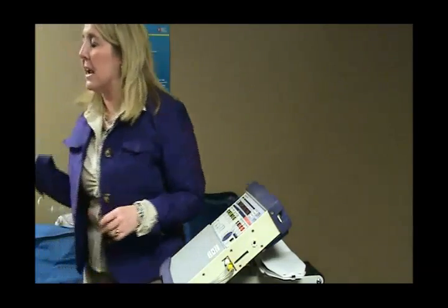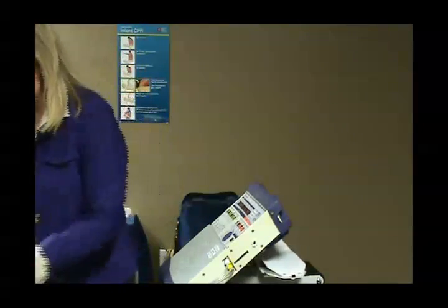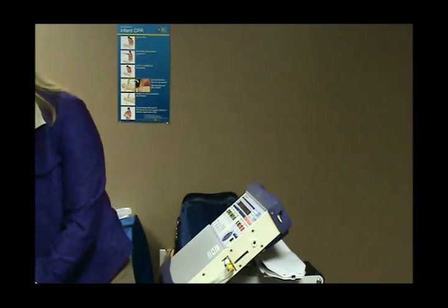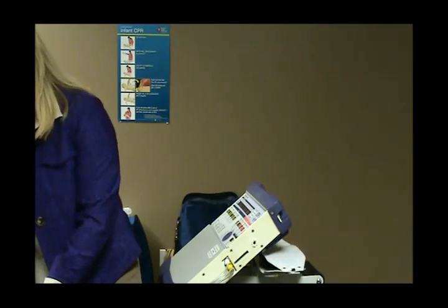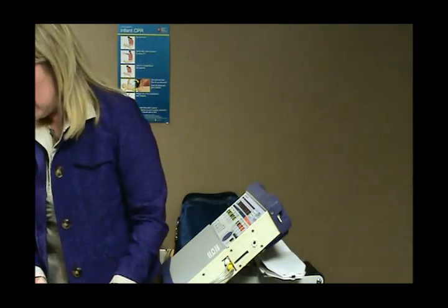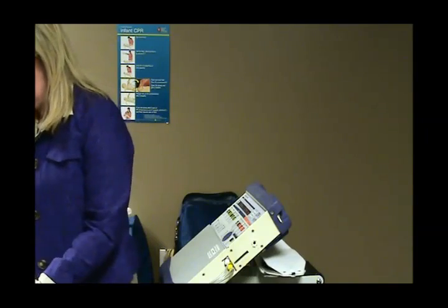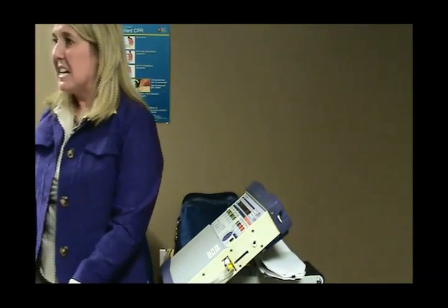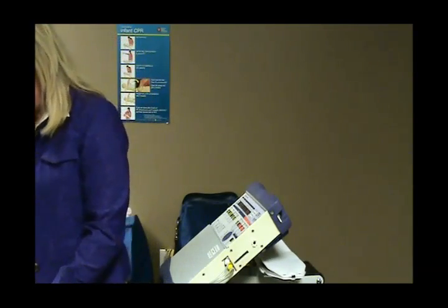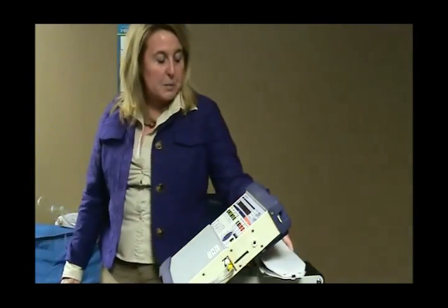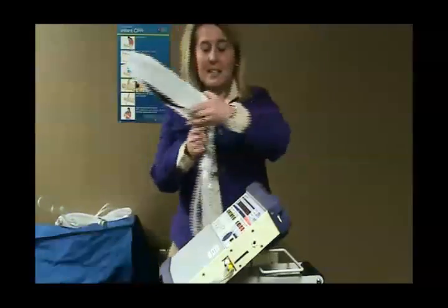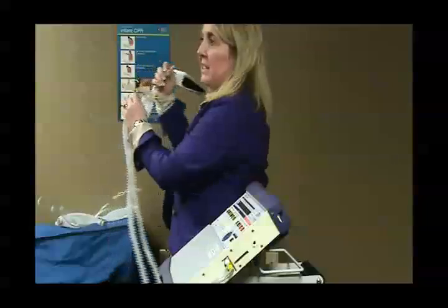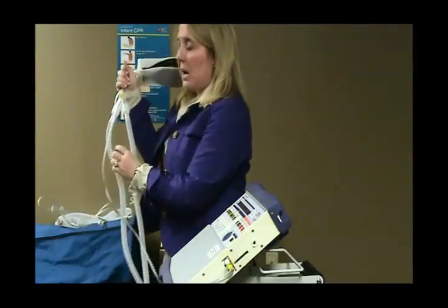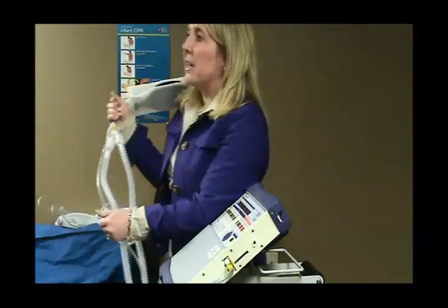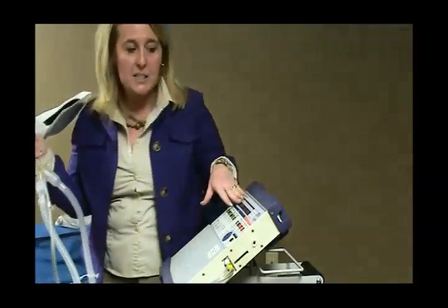Okay. Let's go over error messages, going back to the handout. We have about 15 minutes more. Okay. The upper right-hand corner, the slide that says error messages, disc sense. The disc sense message, disc sense means that the ventilator is not sensing flow in these 2 flow tubes. Okay? So let's say, for example, the ventilator alarms, you glance over at it, it says disc sense.